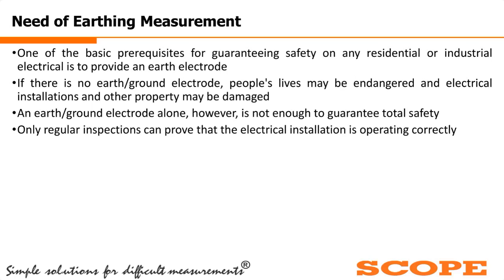Then the next one is that regular inspections are required, because the earthing resistance may vary due to the various parameters we had seen in the previous slide, that is, corrosion or any type of environmental parameters. So we have to always monitor this earthing resistance periodically to ensure the user safety.